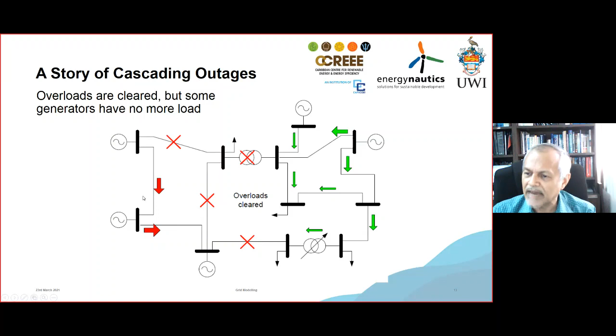Because of that, I have more problems in the system. I lose more lines, and it continues to lose more lines. More power is being taken from these generators here to take up the slack. I get an under frequency, over frequency problem because I've removed this line. This generator continues to generate, but there is no way to put the power, so in the instantaneous mode, this goes to over frequency and trips.